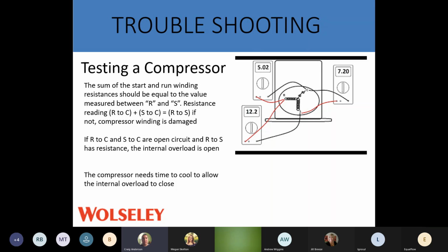Another thing to check as well is if the compressor is warm. If you can't put your hand on that compressor, chances are the internal overload is open. So if you go from R to C and S to C and they are open circuits, and your R to S has some resistance on it, then we know we have an internal overload that's open on the compressor. So you have two options at this point. Get some water and try to cool down that compressor to see if we can get that overload to close again, or you're going to tell the customer, I'll be back tomorrow, this unit needs to cool down. Once it's cooled down, if the overload is still open, then we're looking at changing a compressor.